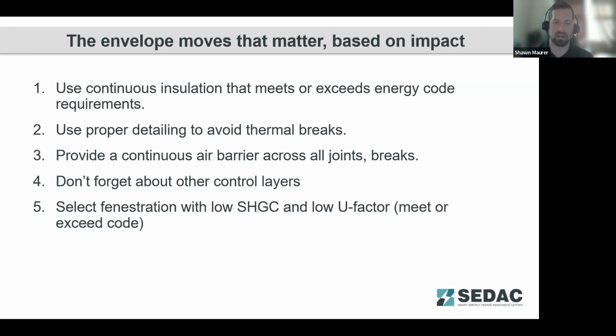You want lower U factors so that you've got improved insulation from those window assemblies. Really trying to enforce here that you want to exceed code. Code is kind of that bare minimum compliance requirement. It's like getting a D on a test. You just passed. So if you can go beyond the code in any ways and then trade off somewhere else as far as sizing of your HVAC equipment or the amount of lighting you need to install in a space, then we highly recommend that you focus on those areas to improve the envelope first.